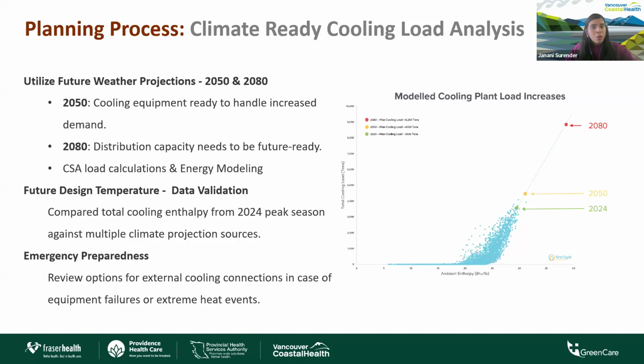And this whole thing is due to the rising ambient enthalpy, which means that as the temperature gets hotter and more humid, it not only increases the cooling demand, but also reduces the overall cooling system's efficiency. And this is very important, which is why we are planning for future climate conditions. So designing our cooling equipment for 2050's climate demand and our distribution system for 2080 climate conditions was our priority.